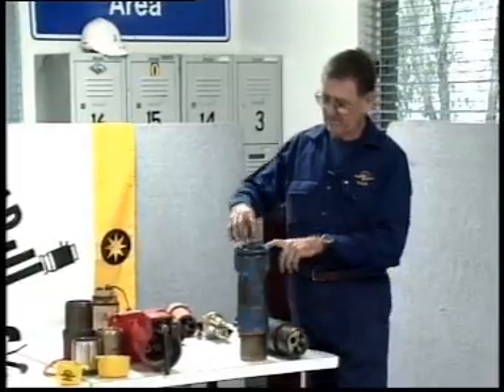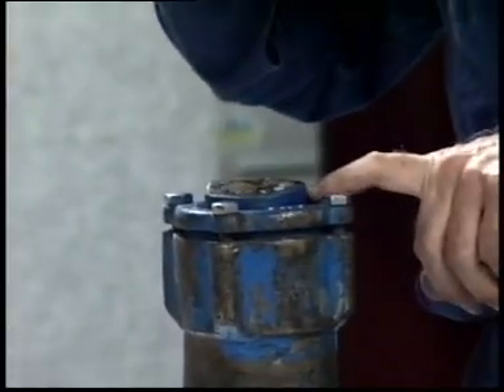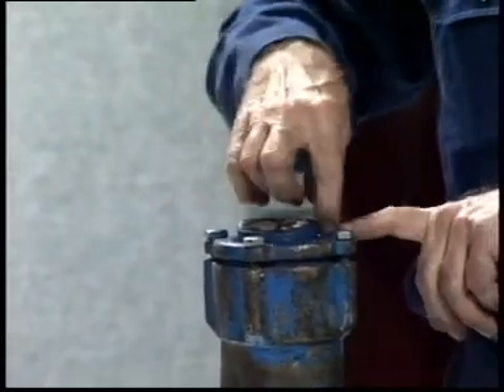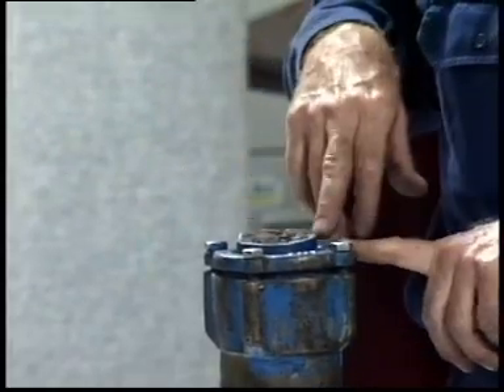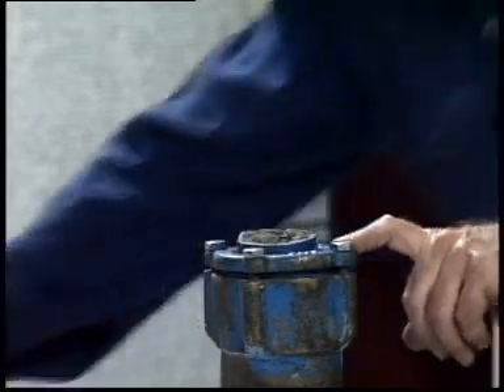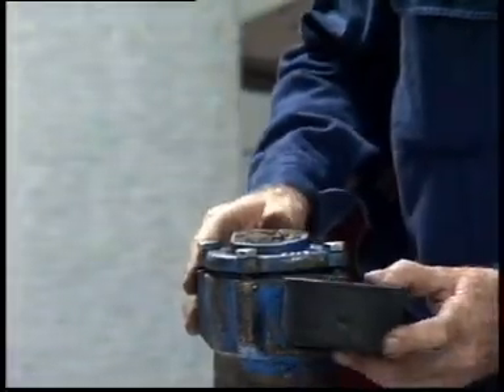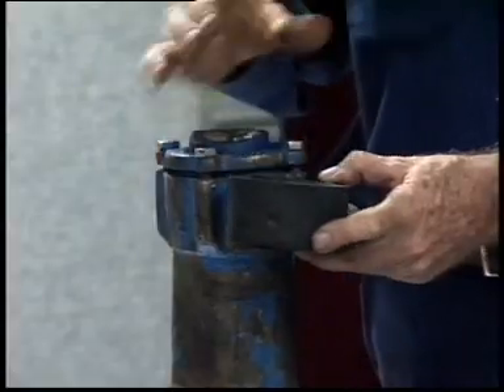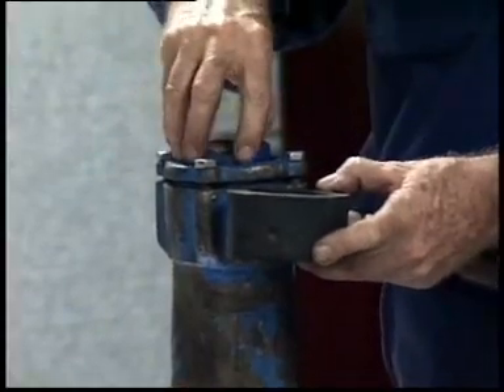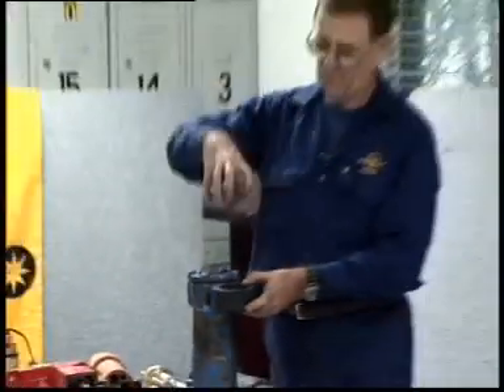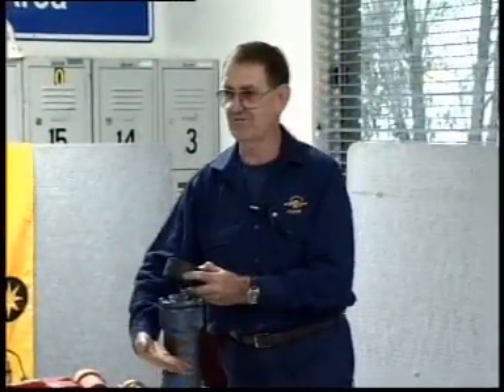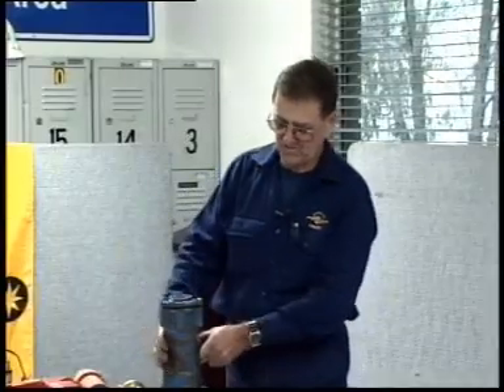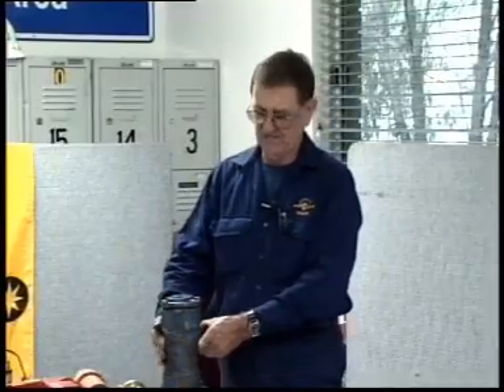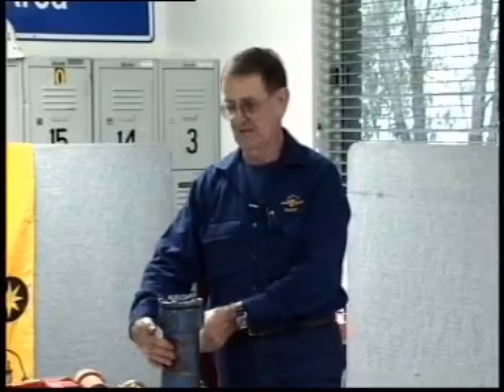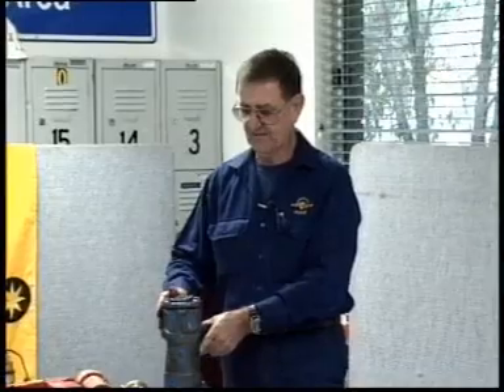When you look at the back of the plug, you'll find that there's a painted section on the cable where it comes out the back end here. That's for our convenience. It's called a witness mark. And when these cables come into town, one of the first things we normally do is have a look to see if that witness mark is painted all the way down to the neoprene cone that sits in there and clamps the cable in the back end of the plug. Now, if it doesn't, if we can see black rubber there, there's a fair chance that that cable has been stretched and pulled in the plug. Invariably, that's where we find the fault, is in the plug end. This particular one here is squashed flat on both sides. It was run over by a miner, and that's where the damage happens to be. So we've just cut it off and kept it. So that's the witness mark.